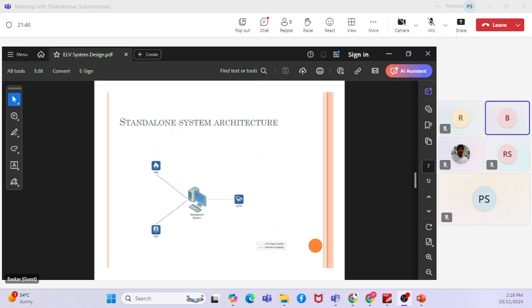When we talk about the standalone system, either the fire alarm, intruder alarm system, or CCTV system is just connected to one server and monitored. It will not be connected to the outside environment. The main disadvantage is that if you want to monitor from anywhere, you cannot, because it's a standalone system. For fire alarm, CCTV, access control, or intruder alarm systems, we need a system that is connected and monitored remotely. That is the requirement nowadays, which has to be checked in the specifications and followed while doing the design.